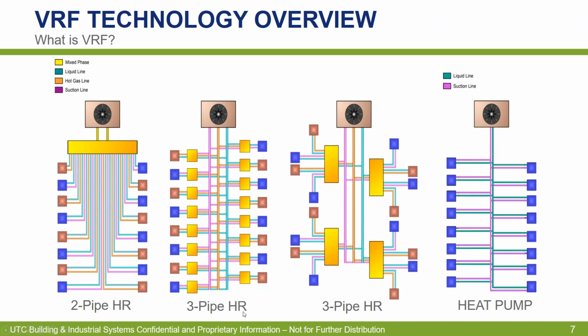Now, a different style heat recovery is our 3-pipe heat recovery system. This diagram right here is showing single port flow selectors feeding each respective fan coil.